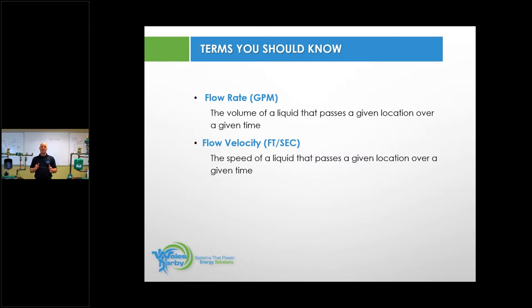The reason we want to be between 2 and 4 feet is that's where we'll have a nice, flexible, quiet system. If we were to start moving water at 6 feet per second, we will start to create noise within the piping. And if we were to move water at 8 feet per second, we will start to erode metallic pipe. So again, velocity is important, and we're going to go through sizing of circulators and help you figure that out.